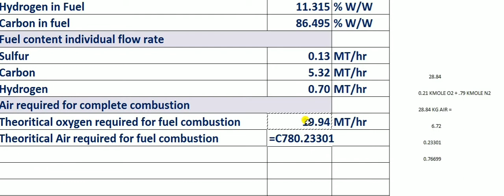So you put this molecular weight, 28.84 kg of air, which is equal to 0.21 into 32, 6.72. So 6.72 divided by 28.84 will give the oxygen 0.23301 in 1 kg of air. So how much air you require, this divided by 0.23301, 42.66 tons per hour of air you require, correct?